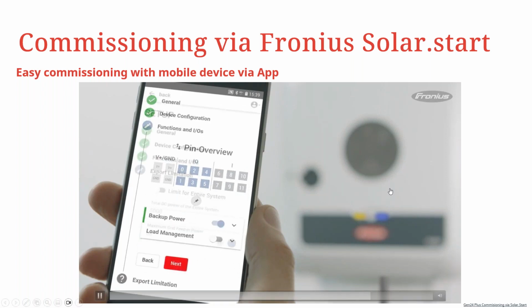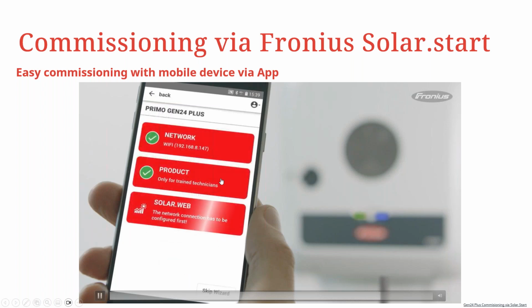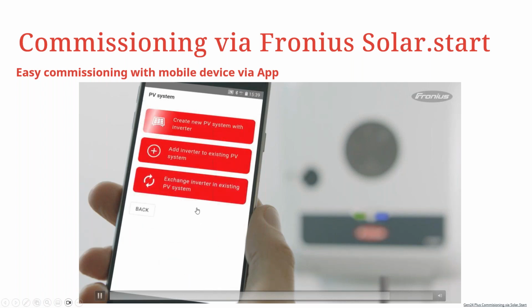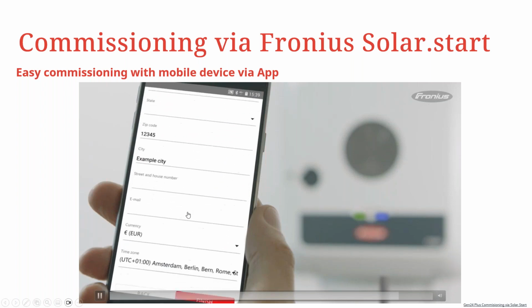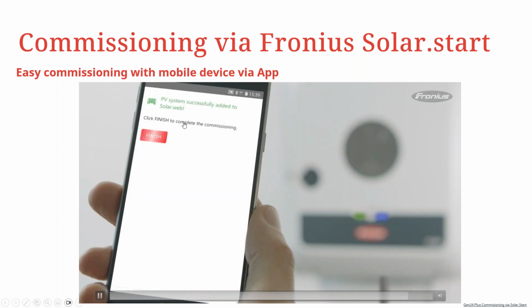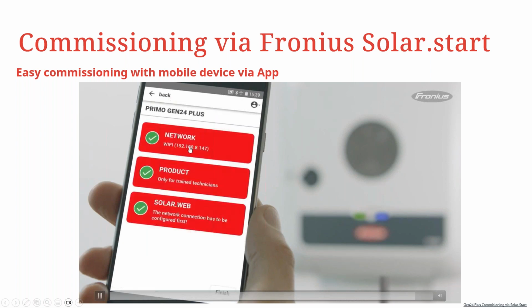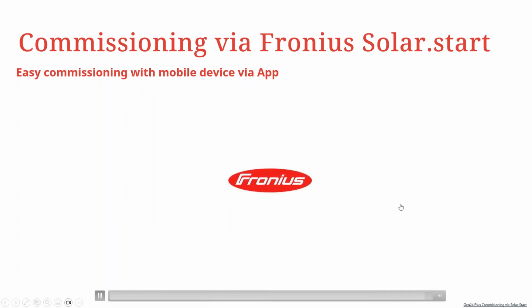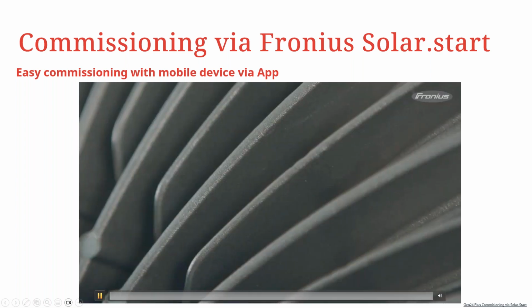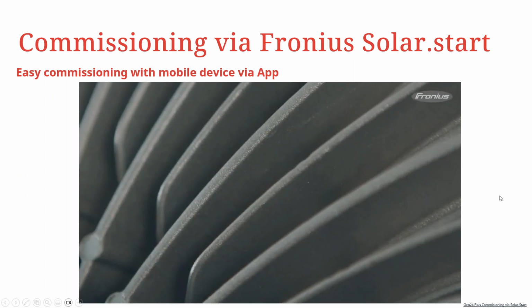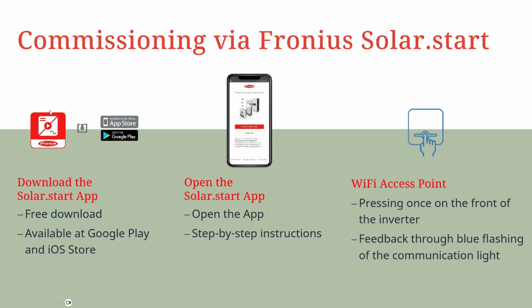As you can see, if you want to implement load management, you can do so. If you want to implement export limitation, you can also do so. Then followed by the registering of the device to SolarWeb. And then once that is done, you can now finish your commissioning, and you have that your system has been successfully added to SolarWeb, and your commissioning is done by, of course, seeing the checks on the 3 user-friendly process steps as earlier mentioned. So that's basically it. Just to round up, you have 3 basic processes: download the SolarStart app, open the SolarStart app, and then access the Wi-Fi points of the inverter, and then continue with the commissioning as described.